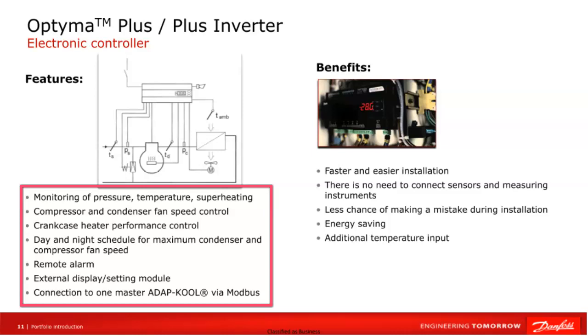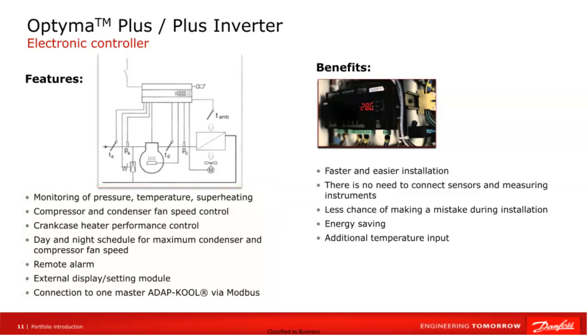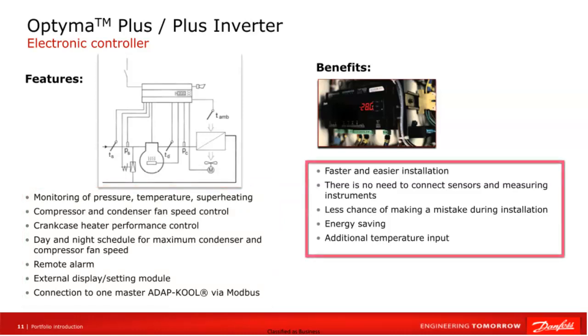Features of the electronic controller: superheat, pressure and temperature monitoring, condenser and compressor fan speed control, crankcase heater performance control, day and night operation schedule ensuring maximum condenser and compressor fan speed, possibility of remote alarming, external display setting module, and possibility to connect to the ADAP-KOOL system manager via Modbus. Advantages of the electronic controller: faster and easier installation. There is no need to connect additional sensors and measuring instruments. Reduced risk of errors during installation. Energy saving. Additional temperature input.